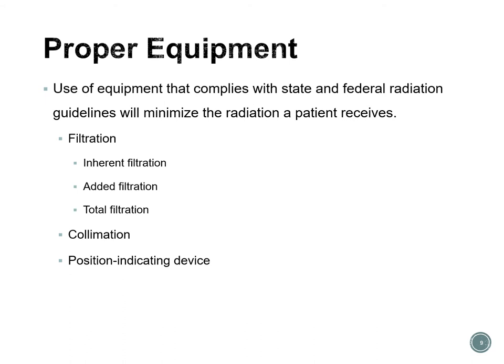Proper equipment means using equipment that complies with state and federal radiation guidelines to minimize the radiation a patient receives. We're going to talk about filtration—the differences between inherent filtration, added filtration, and total filtration—as well as collimation and position indicating devices. The x-ray tube head should be properly equipped with aluminum filters, a lead collimator, and a PID in order to do the best job we can for our patients.